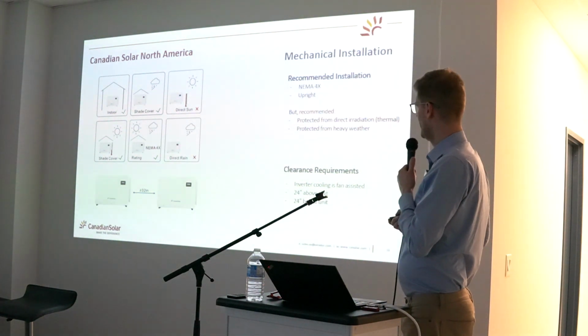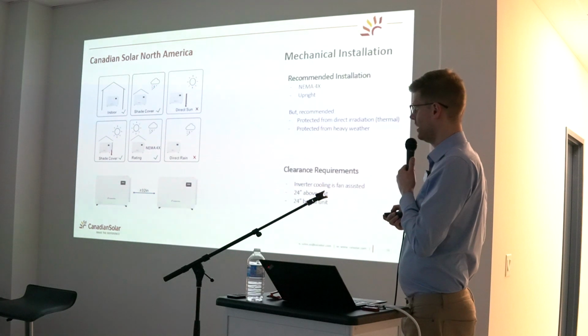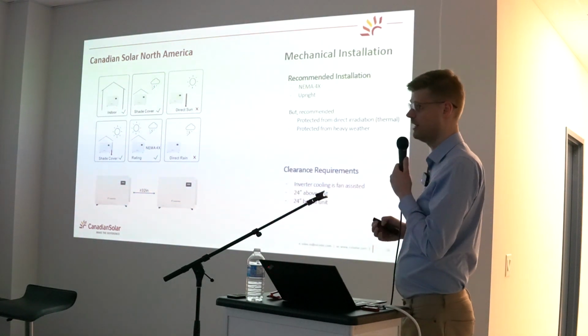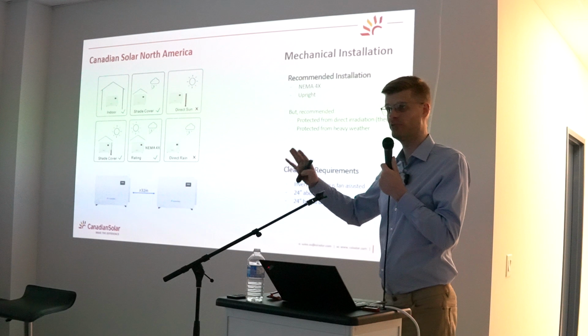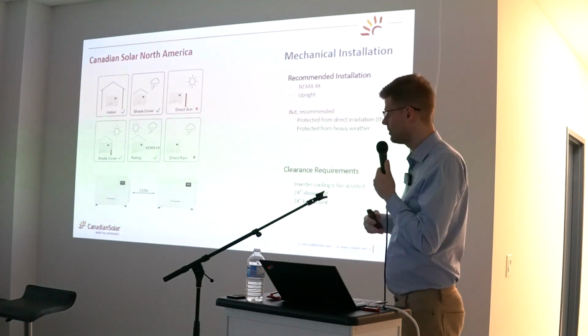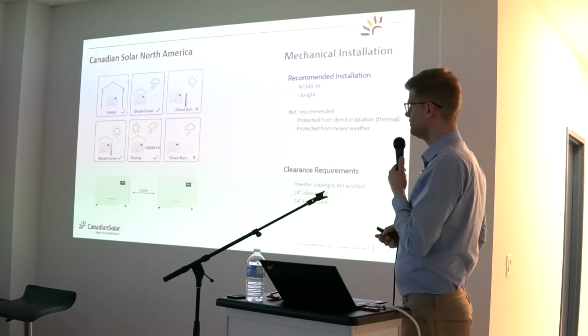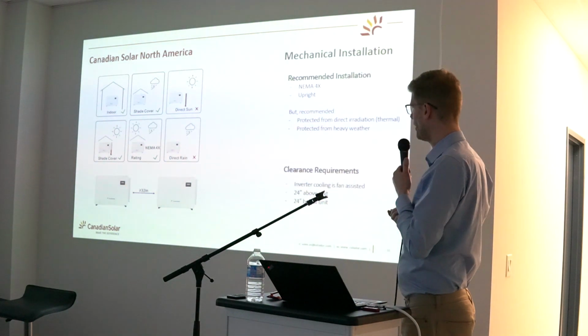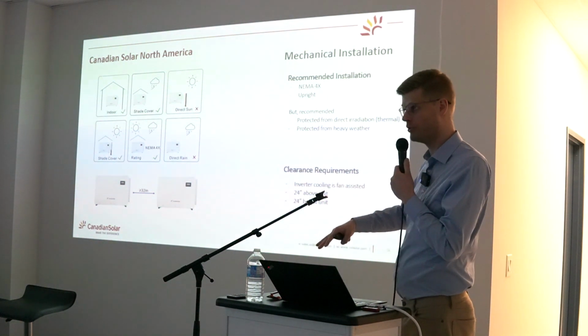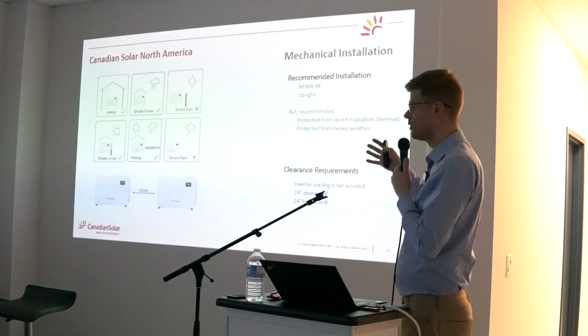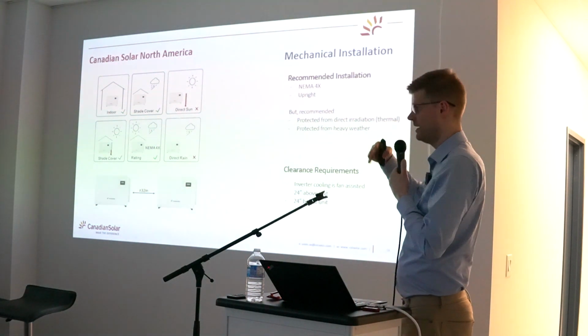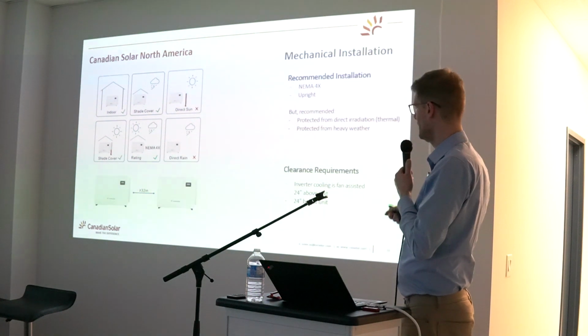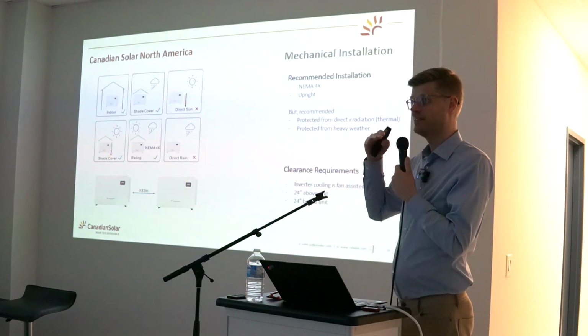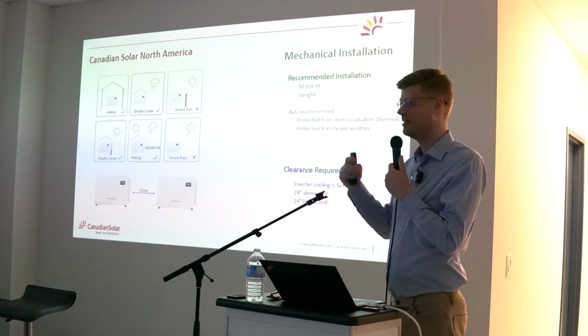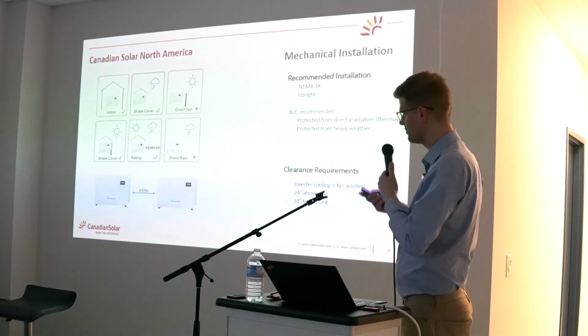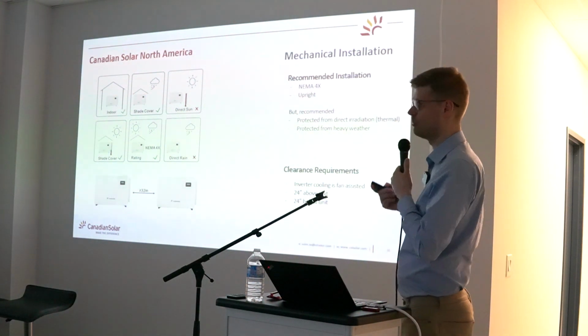The distance here from one inverter to the other is specified at 32 inches. That's something if you line multiple units up on a rooftop rack like a unistrut directly besides the array, just for access. Bottom and below, for snow accumulation on your roof, you should have at least 2 feet. And if you place it on or underneath a little rooftop system or little shade cover, you need to have another 2 feet on top, that the heat exhaust to the top of the inverter is well dissipated and is not blocked by any cover.